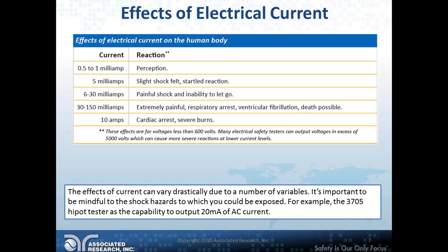Being able to recognize what hazards you'd be exposed to is the first step of this whole process. Let's say, for example, you have one of our 3705 high-pot testing instruments. It's an AC high-pot testing instrument, and it can output a current of 20 milliamps. 20 milliamps, that's a painful shock, possibly the inability to let go.